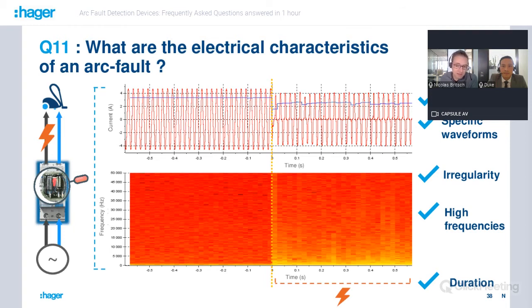And finally, the duration of the fault. Of course, we are looking for something repeating over time for several half cycles, not only one half cycle, which means tens or hundreds of milliseconds, depending on the current value, because the more current we have, the faster the tripping shall be.